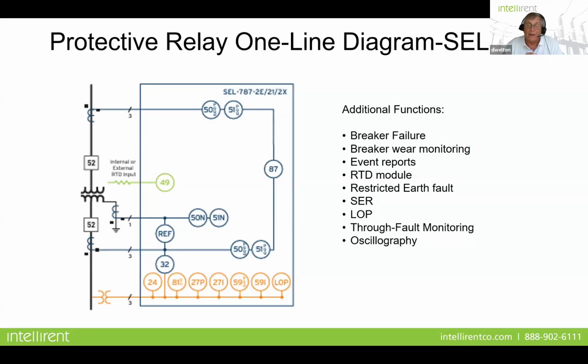Well, what was evident when he started to look at the fault record was that there was no differential trip. The relay had actually nuisance tripped, with an internal error on one of the processors. So it's very important that when you set a relay, you set these types of additional functions and capabilities, so in the event that there is a problem, you have the means to look at things.